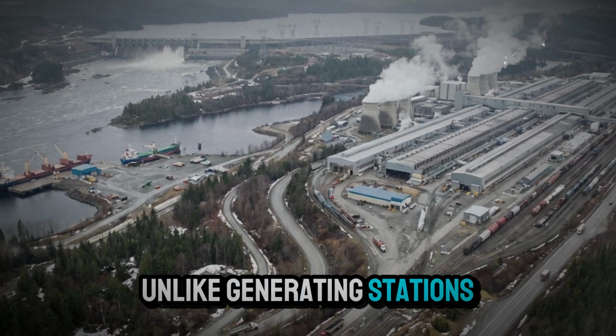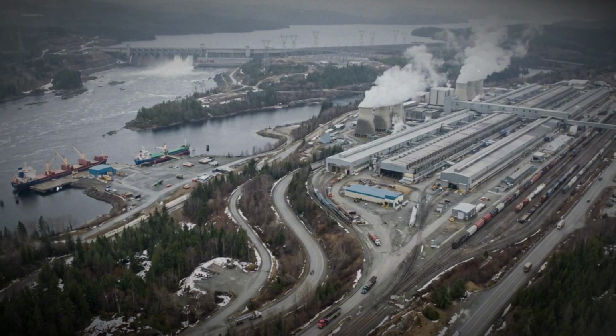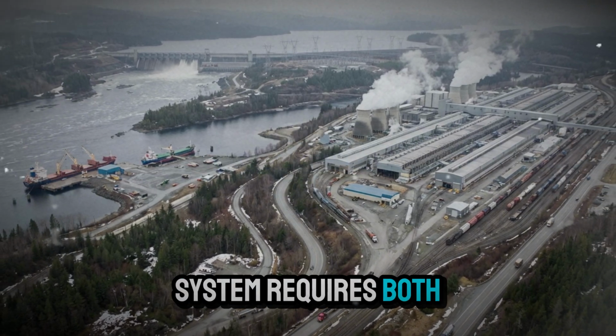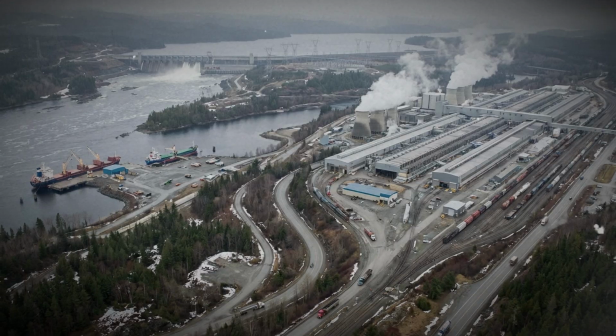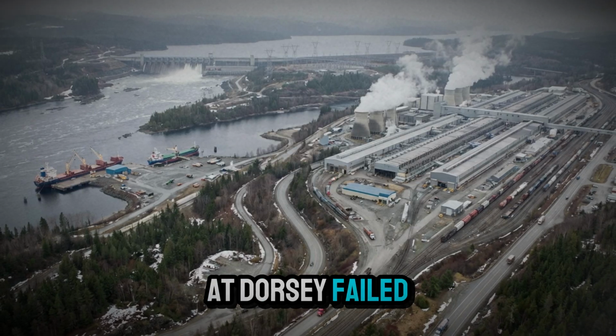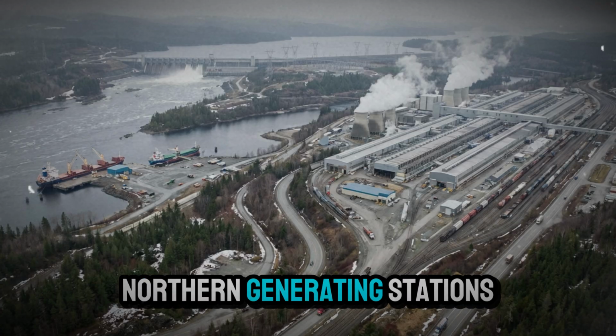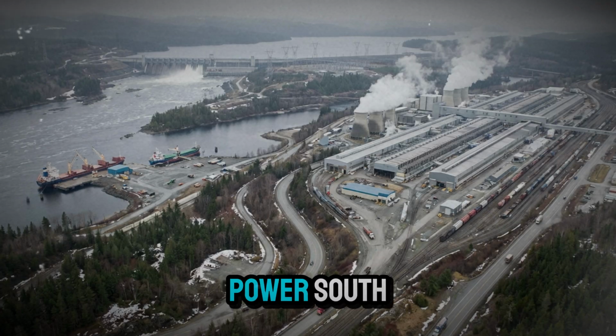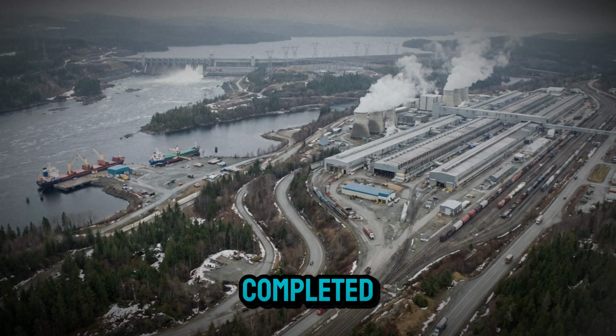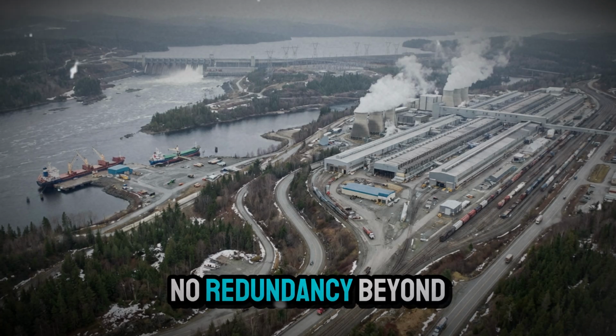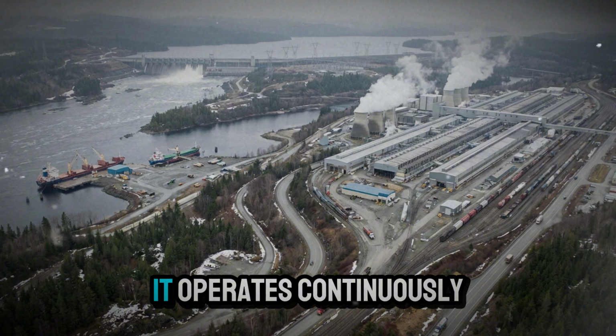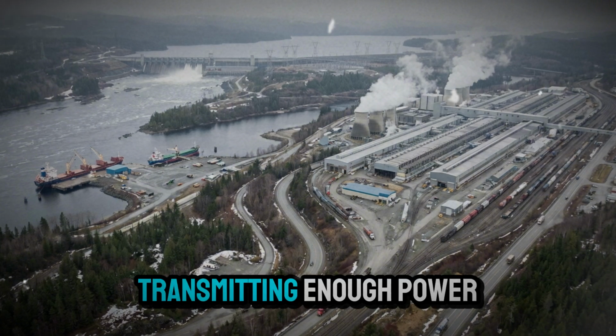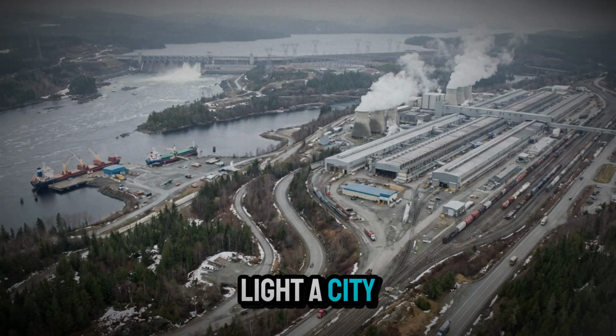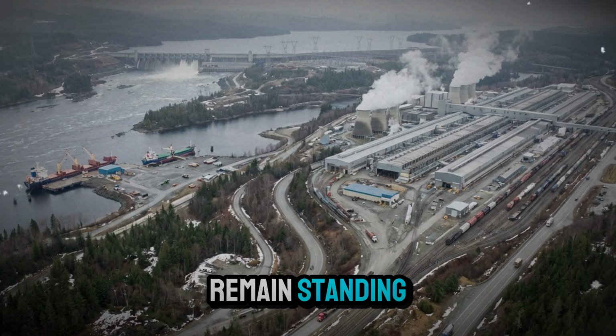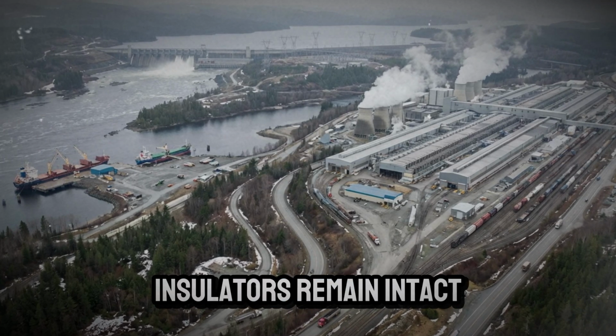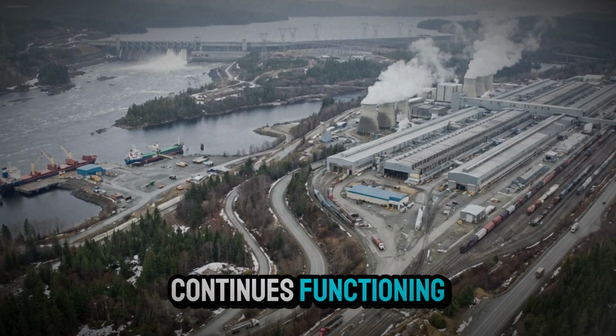Unlike generating stations that can be restarted independently, the HVDC system requires both ends operational simultaneously. If converter equipment at Dorsey failed catastrophically, northern generating stations would have no way to deliver power south until repairs were completed. The system has no redundancy beyond the 3 bipoles. It operates continuously, transmitting enough power every second to light a city, trusting that towers remain standing, insulators remain intact, and converter equipment continues functioning.